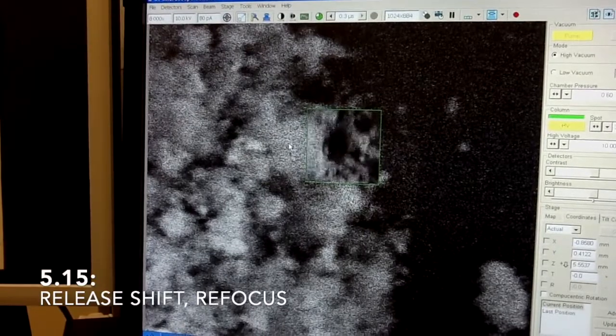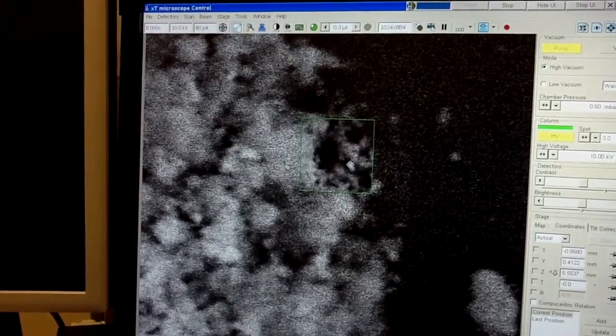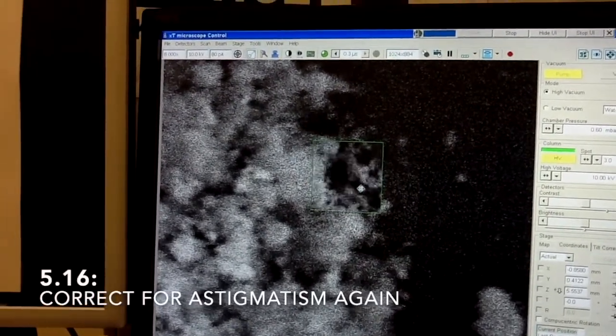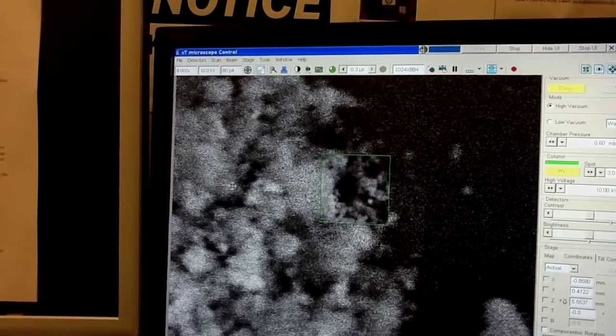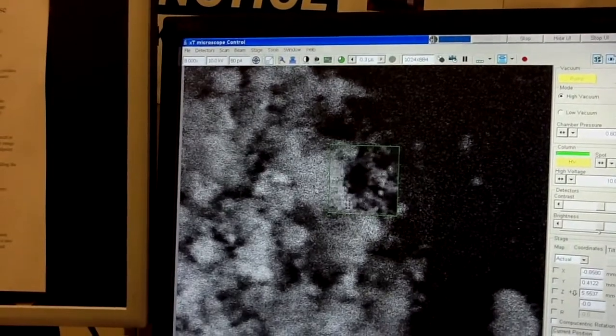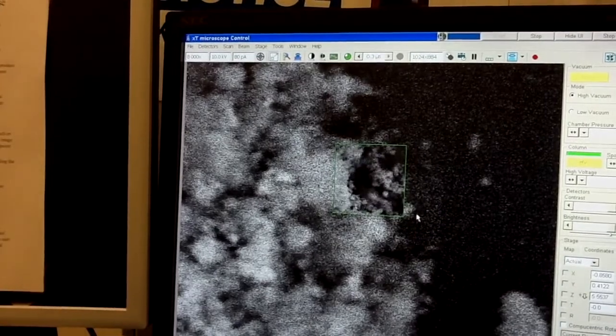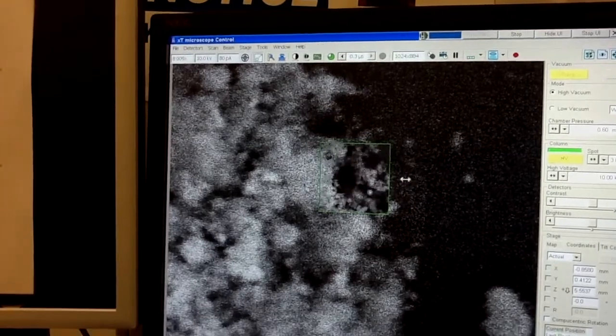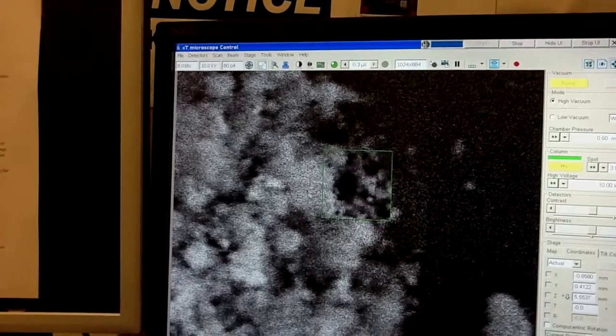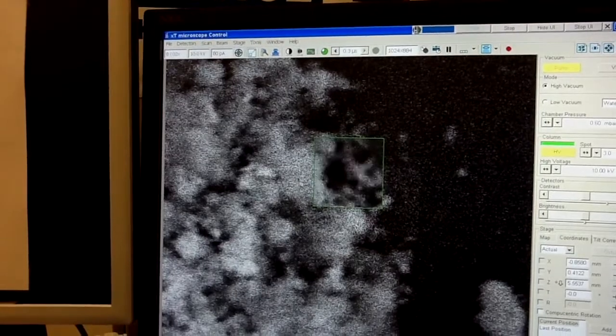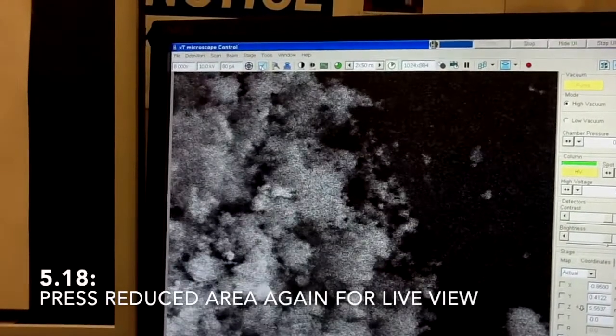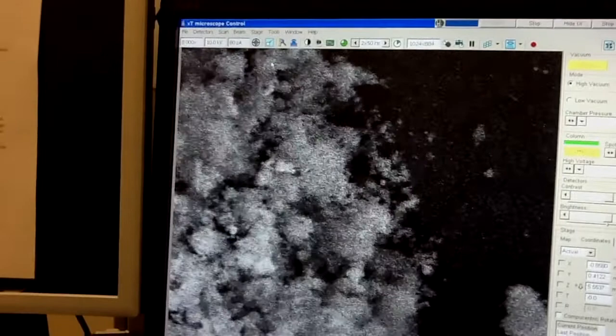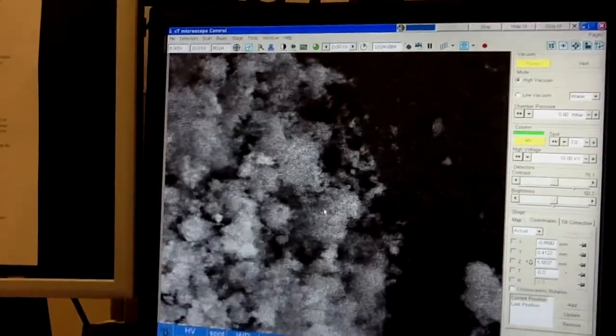So, try to focus as best as you can. Then, release the shift button and try to focus, improve the focusing. So, if you think this is the best focusing, now do the same astigmatism correction. Hold the shift button and move left to right until you think it's the best focus. And up to down or either down or up until you think it's the best focus. And again, release the shift button and try to refocus. Right now, you can see that we don't see this elongation anymore. The image just is out of focus, but there is no elongation in any direction. And that's what you want to get. And if you see this, it means that you remove the astigmatism or majority of it. So, with this, you are pretty much ready to take the image.